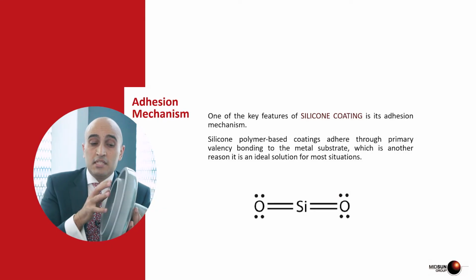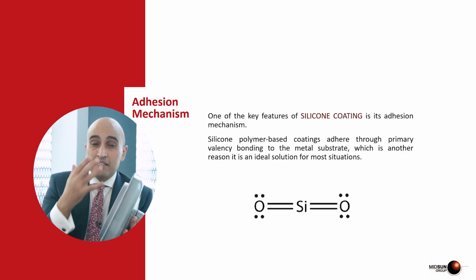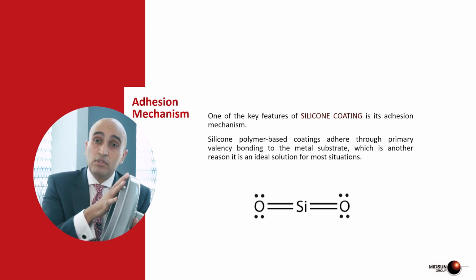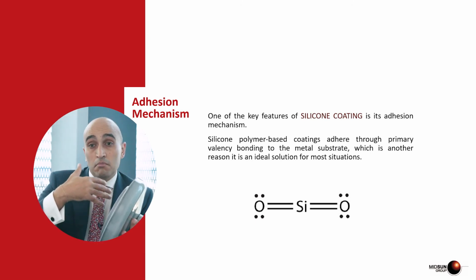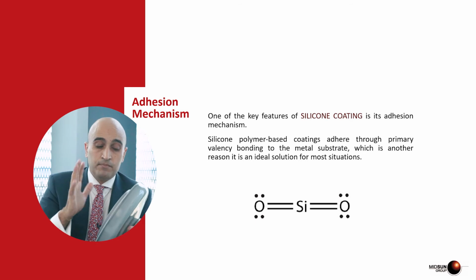The third, and one of the most important, is the adhesion. Once RTV coating is applied in the correct way on the surface of the insulator, it is very difficult to remove. This adhesion will guarantee that the RTV will keep performing throughout many years, a minimum of 10 years.